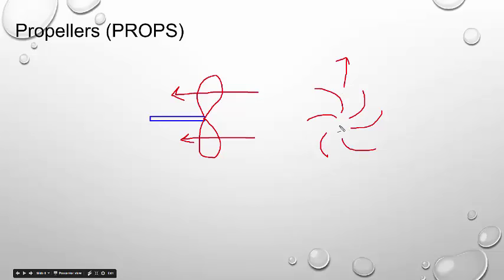So if I draw my impeller like this, I'm going to get what we call axial versus radial flow. So water comes in to this. So if I could draw a line, an arrow coming directly into the eye and then traveling out, kind of perpendicular to the eye, that's going to be radial flow. And then often I have mixed flow, which I get often with these fully enclosed impellers where flow is going to come in this way and then around and out. And that's going to be mixed flow. So a little complicated there. We'll talk about that more.